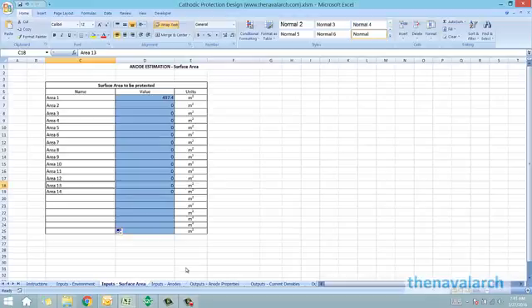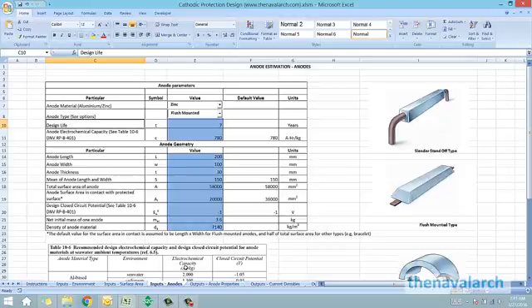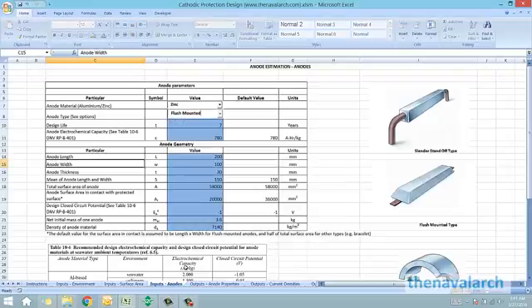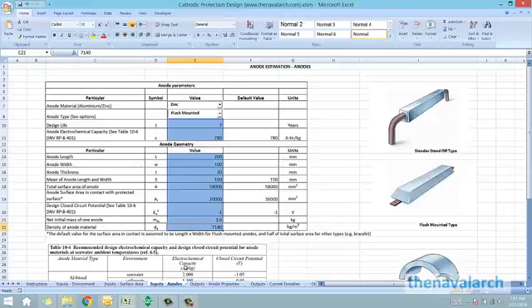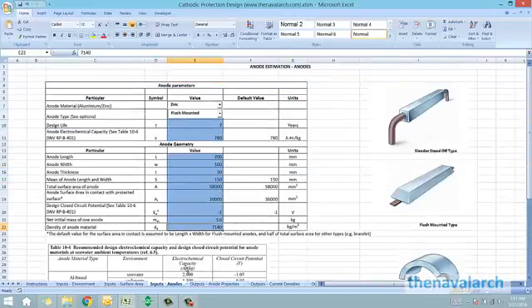Next is the input on the anode properties. The user needs to select the anode material and the type of anode. They also need to provide certain properties like the design life of the anode, the electrochemical capacity, the geometrical properties, the mass of the anode, and the density of its material. Tables and figures are provided wherever appropriate to help the user with these inputs.